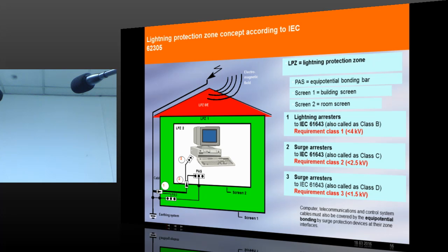And I explained to you in the first slide, origin of installation 6 kV, installation category 4. Inside the building, that means after the first switchboard, installation category 3, and equipments are able to withstand 4 kV. Now this lightning protection standard explains the user of the electrical equipment should ensure that surges in this area are limited to a level less than 4 kV. Further, lightning protection zone 2, surges less than 2.5 kV, surges less than 1.5 kV in a lesser level.